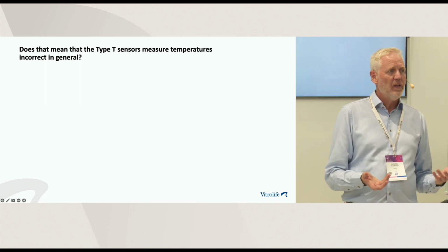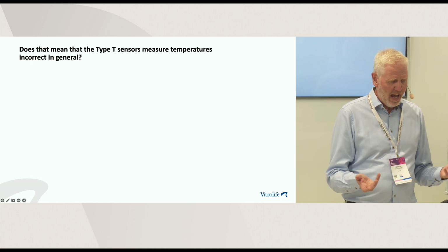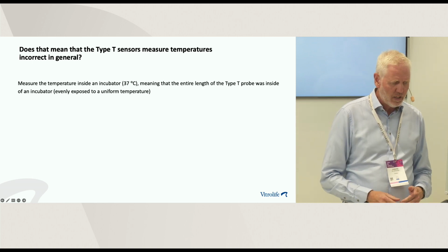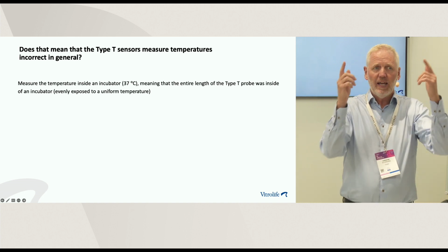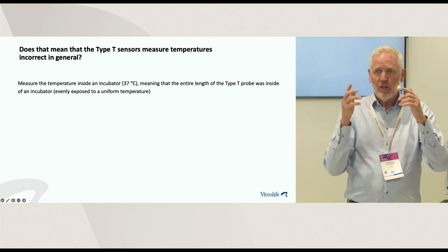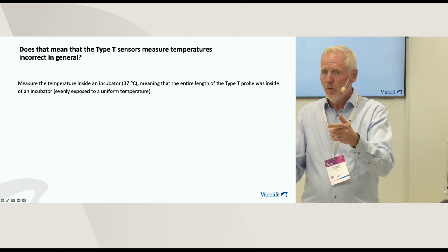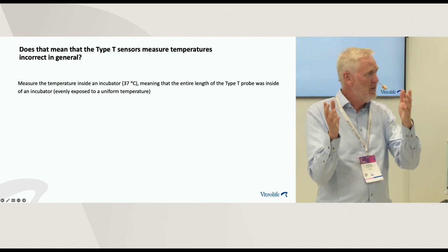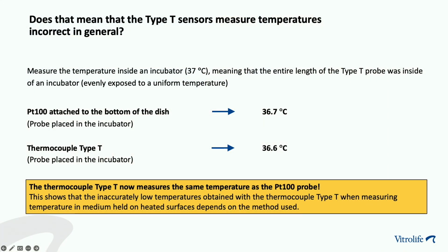So the question is, does that mean that thermocouple type T probes are not working, that they are bad? Or is it something else? So what we did is that we took a thermocouple type T probe and placed it in an incubator, meaning that the entire probe is in the incubator now. We also placed the PT100 inside the incubator, and we measured the temperature in these conditions. And now they measure exactly the same. So the probe is obviously working, but it's not working for that purpose. So the thermocouple type T now measures the same temperature as the PT100, which we didn't see before, showing us that it's the method that's causing the problem. So thermocouple type T should not be used to measure media temperature in dishes on heated surfaces.